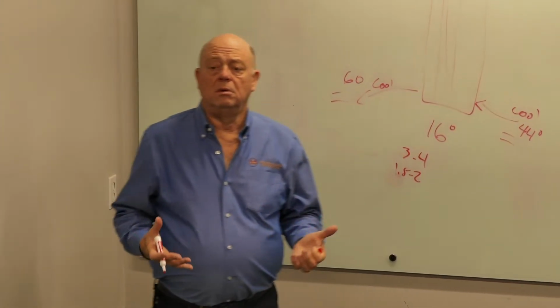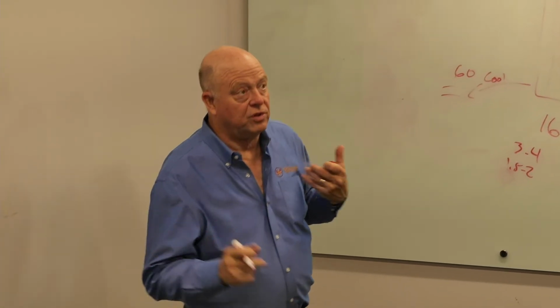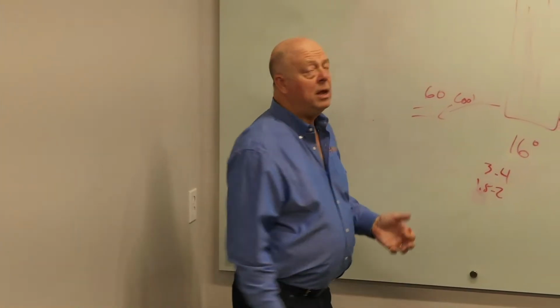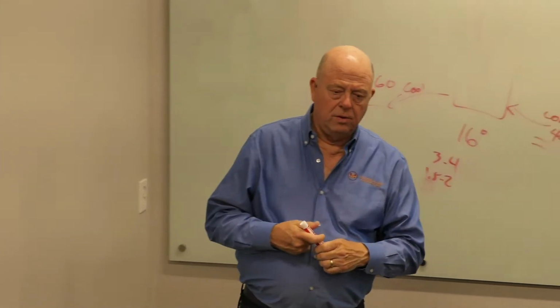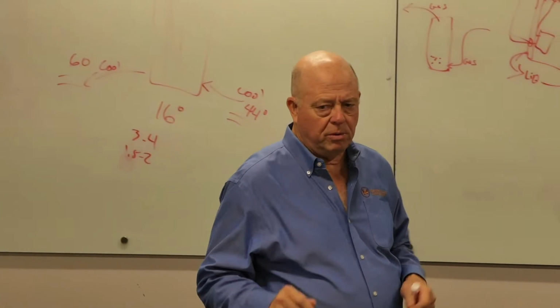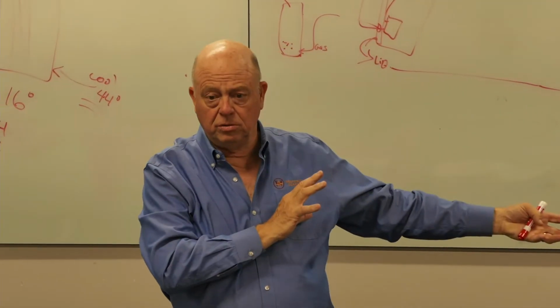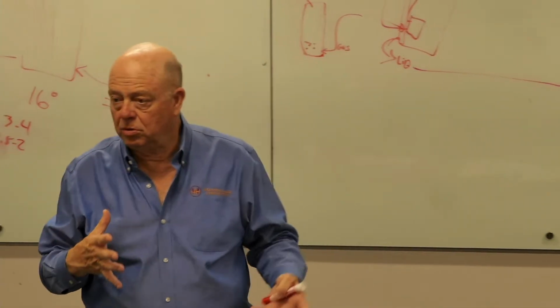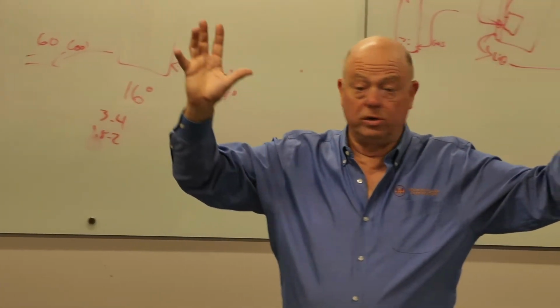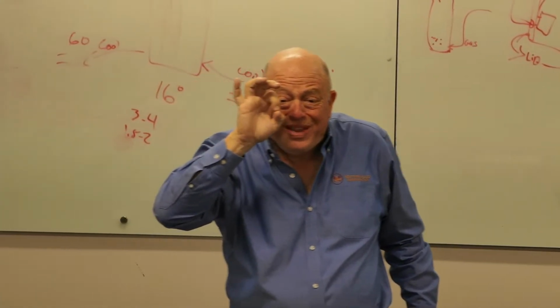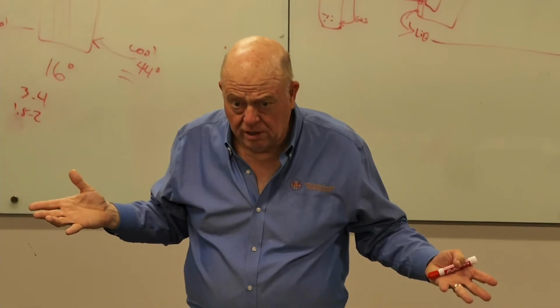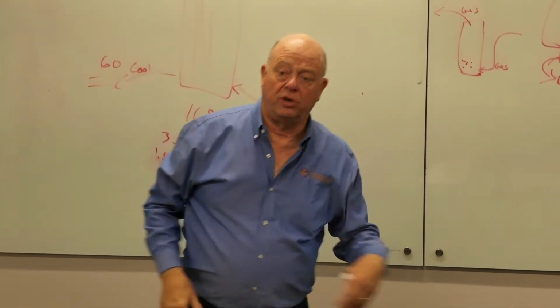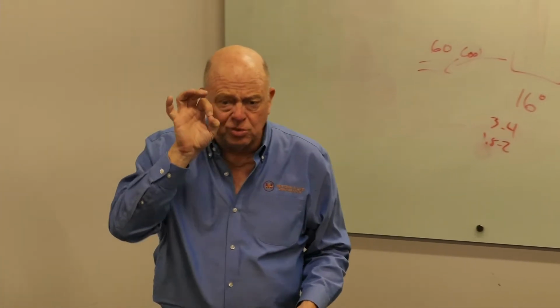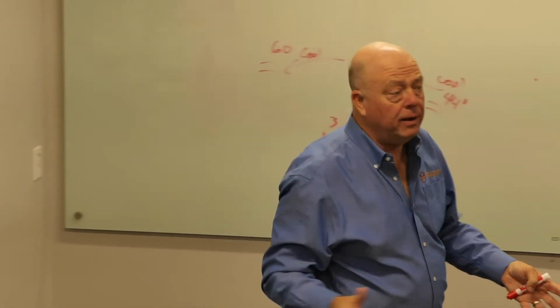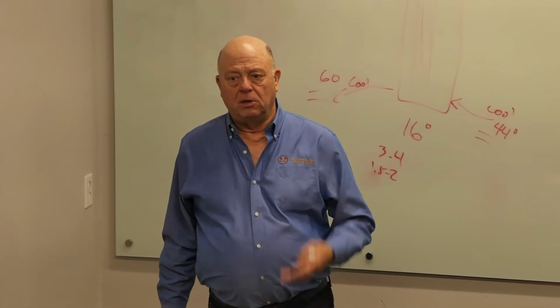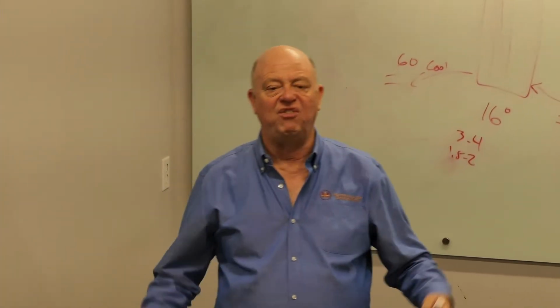And where some people would use them is, we haven't really talked about cooling towers yet, but there's open cooling towers and there's closed circuit cooling towers. And you use a closed circuit cooling tower when you're circulating to water source heat pumps that have teeny tiny little holes in the heat exchanger and they plug up real easy. So you don't want an open tower circulating directly to equipment that's got heat exchangers with teeny tiny little holes. You just don't want that, okay? So you use a closed circuit tower. But closed circuit towers are big, expensive, and heavy.